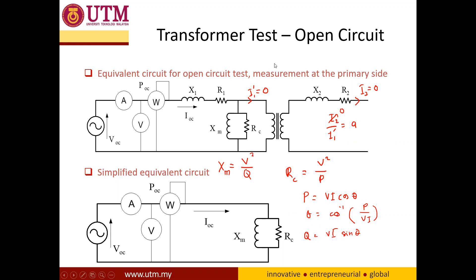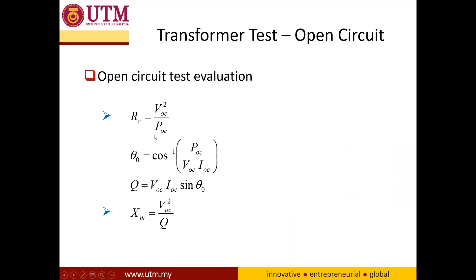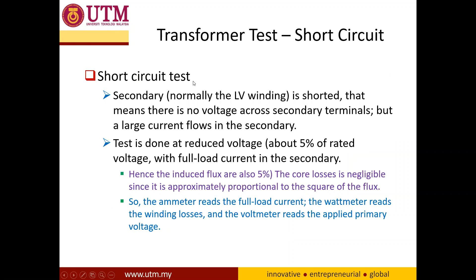So it is straightforward. For the short circuit test, the secondary is shorted and the reading is obtained at the primary side. Since it is short circuit, there is no voltage at the secondary terminal but a very large current will flow. To avoid this, the test is done at a very low voltage — for example, five percent of the rated voltage — so the current at the secondary is considered as full load current. At this low voltage, the core losses represented by RC can be assumed negligible.